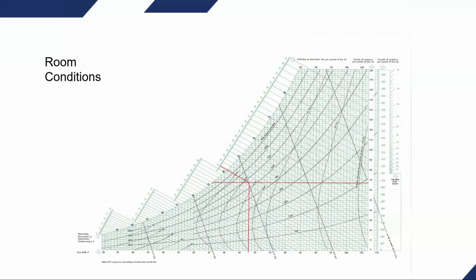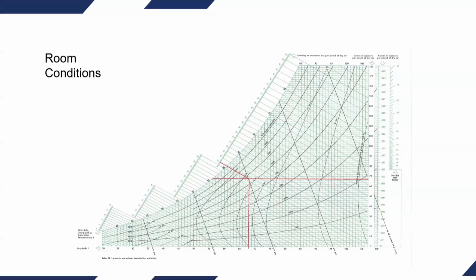You'll also look at that, considering that the outside air is conditioned in this particular case, you're going to have a mix between the conditioned outside air and the room temperature that you've got to remove the moisture from. The room conditions dictated that we needed at least 56-degree discharge air to reach dew point. And most of the units were not delivering that.